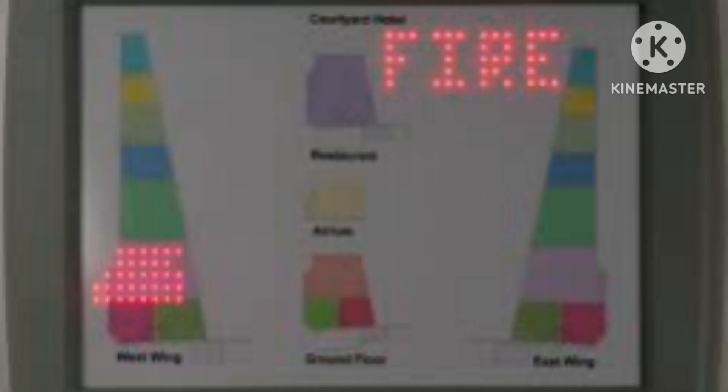Loop voltage too low — check the loop voltage. Check the PSU value in the test engine menu; the normal value is 22.1. If the PSU is not working properly, check it, and if required, replace the power supply unit.